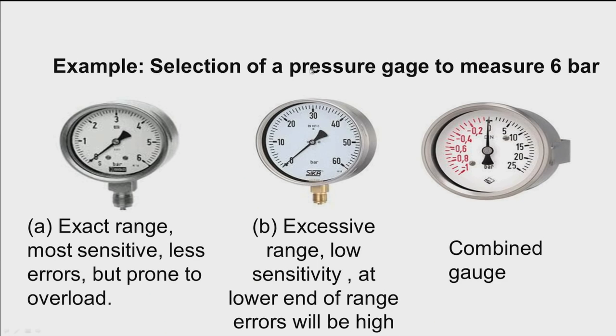For example, in selecting a pressure gauge to measure 6 bar: if we select a gauge with a range of exactly 6 bar, it will be most sensitive with fewer errors but prone to overload if pressure exceeds 6 bar. If we select a 60 bar gauge, it will have excessive range, low sensitivity, and errors will be too high at the lower end of the range.